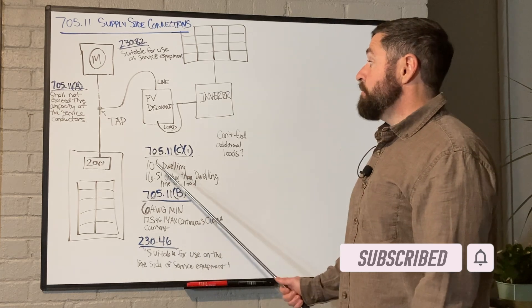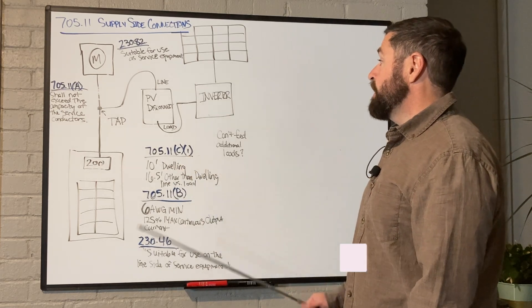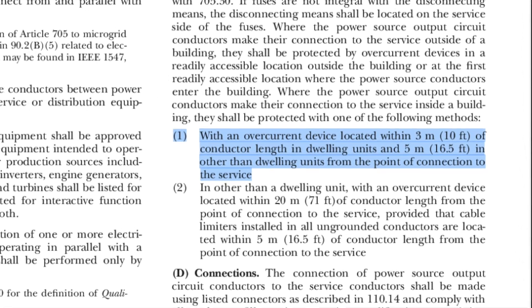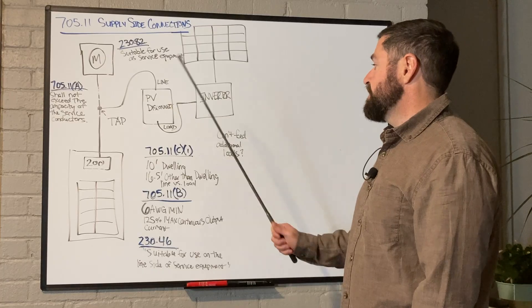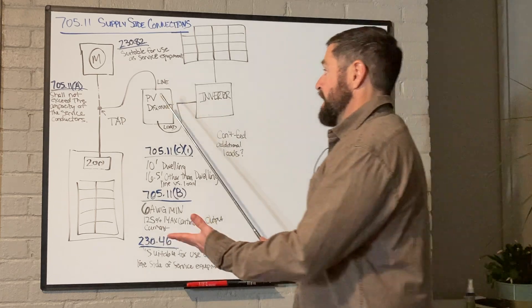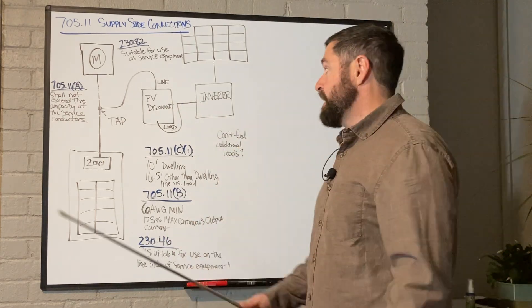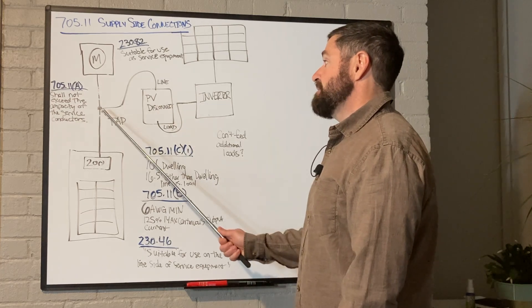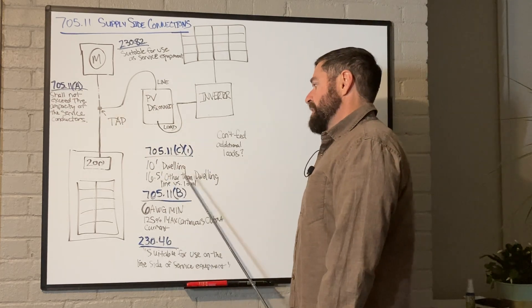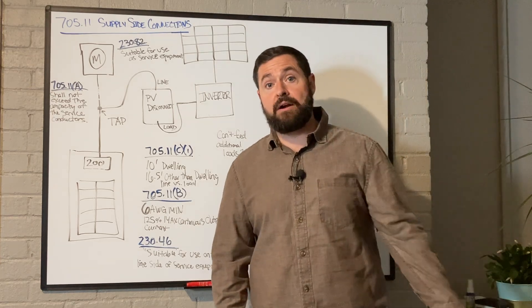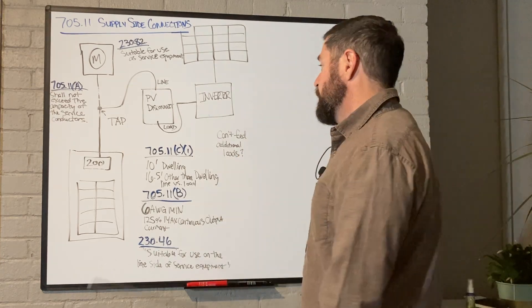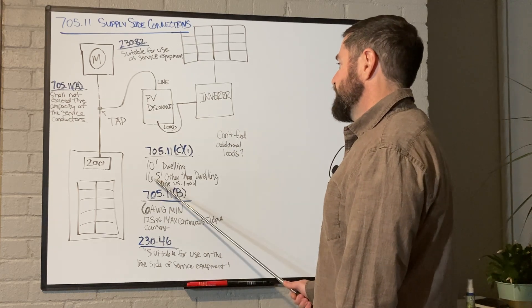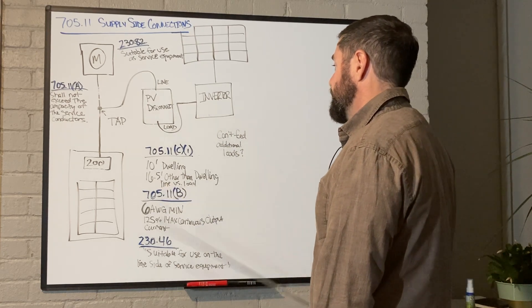So 705.11c1 is in regards to the length between the tap and your overcurrent protection device. So if this is a dwelling where somebody resides, like a home or an apartment, that overcurrent protection device has to be within 10 feet of the tap. If it is something other than a dwelling, such as a warehouse or something of that nature, then that overcurrent protection has to be within 16.5 feet.